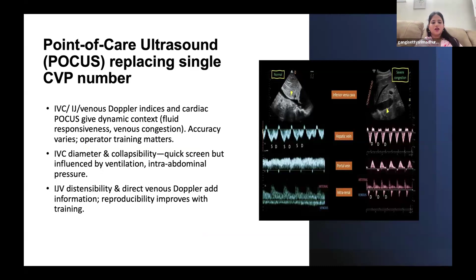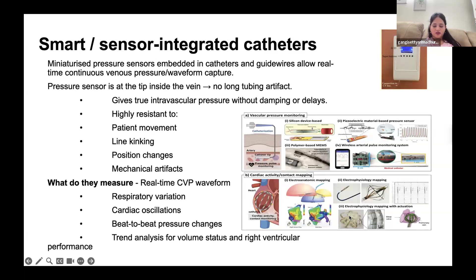Next is smart sensor integrated catheters, where we have miniature pressure sensors embedded in the catheters. Since the pressure sensor is at the tip of the vein, there are no long tubing artifacts, no tubing mechanisms or anything. So we can get a continuous waveform capture. It gives the real-time CVP waveform with the respiratory variations, cardiac oscillations, and beat-to-beat pressure changes, and the trend analysis of the volume status and the right ventricular performance. So these are the newest advancements, built into the catheter itself. There is no tubing or transducer needed for these kinds of catheters.